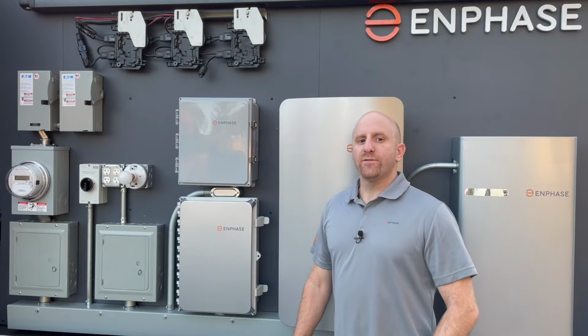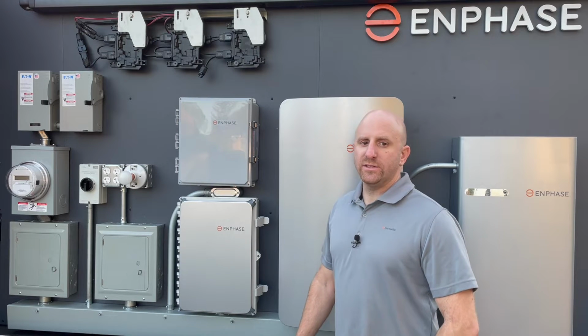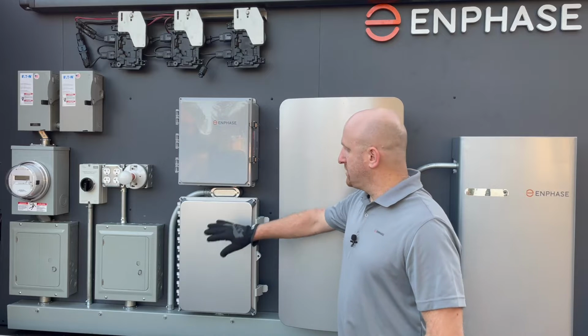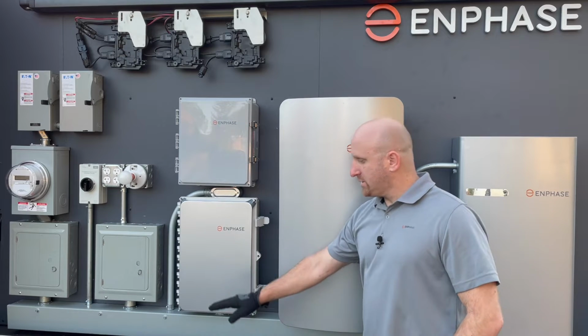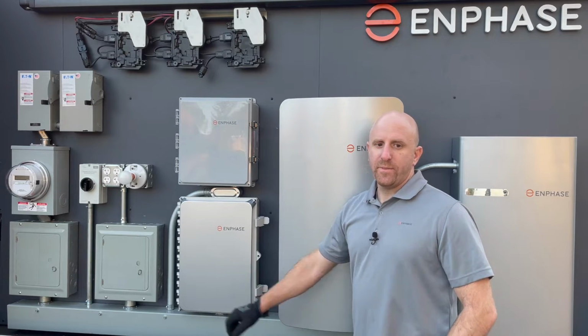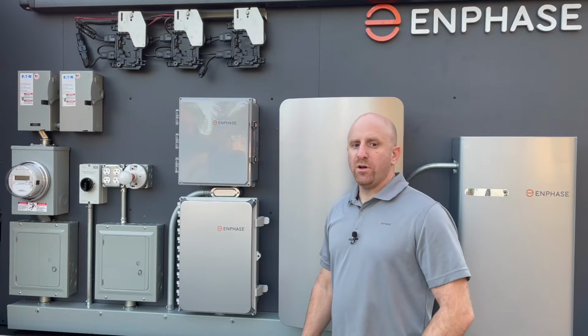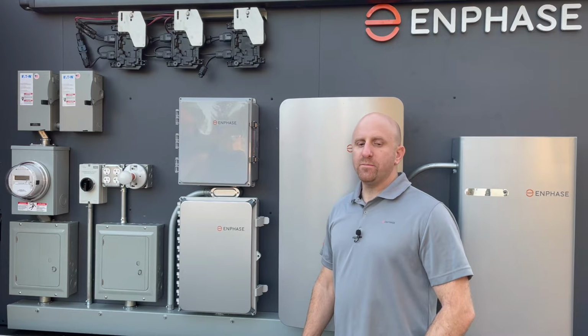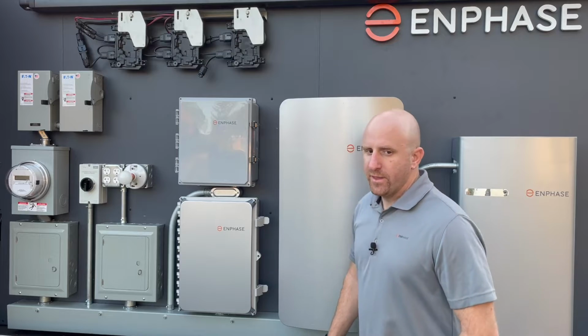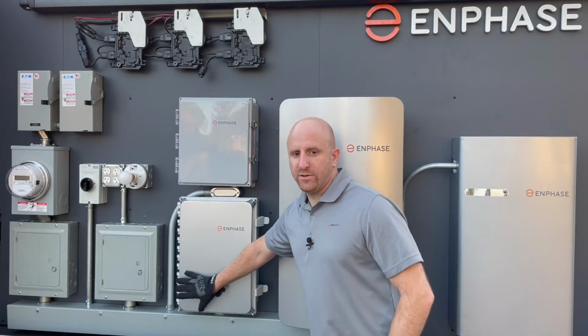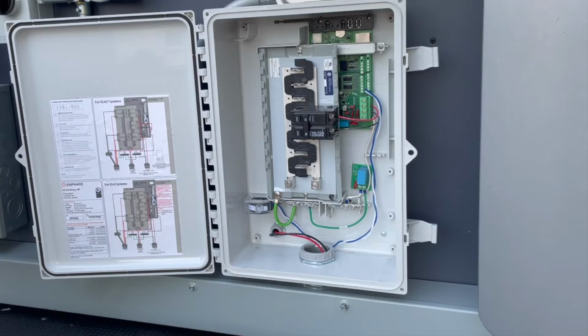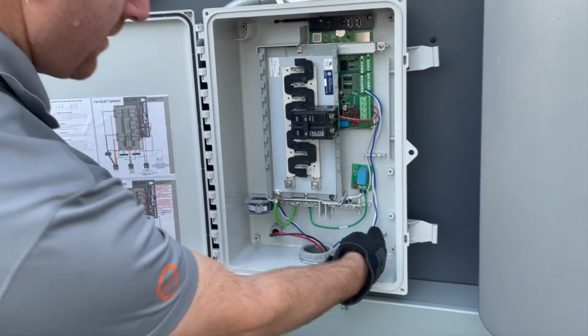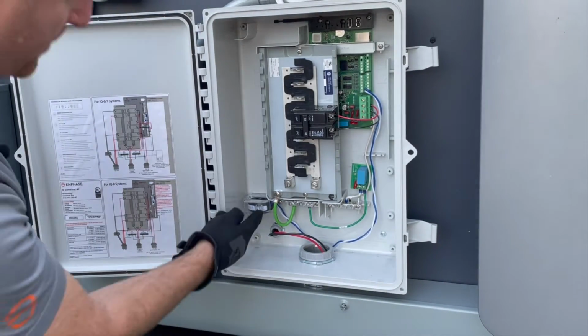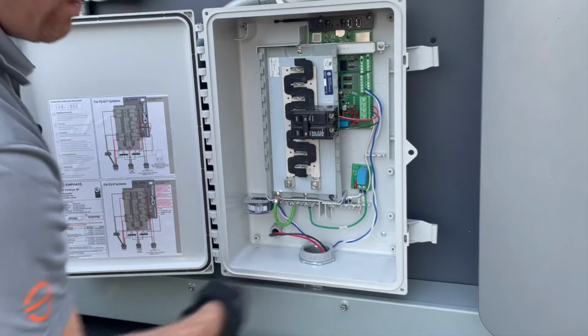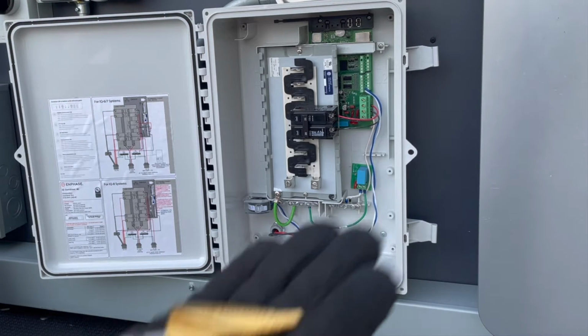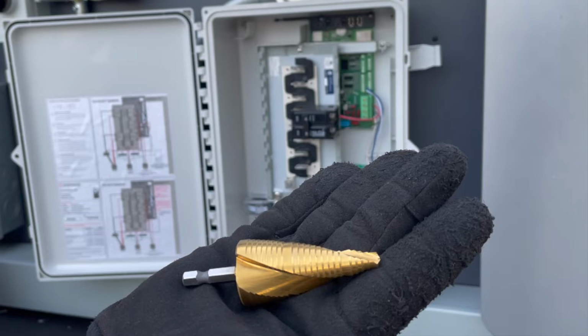It is UL listed for up to a total of 80 amps of PV circuit breakers. The unit is meant to be wall mounted and should be at least 3 feet above the ground. It is outdoor rated, but similar to all electronics, it's best to have some protection from the elements and the sun. Be sure that conduit enters the lower quarter of the box. Sides, bottom, or rear entry is fine, and must be below the ground and neutral bars. We recommend using a step drill bit for the conduit fitting holes.